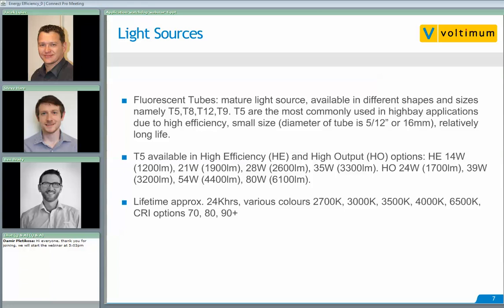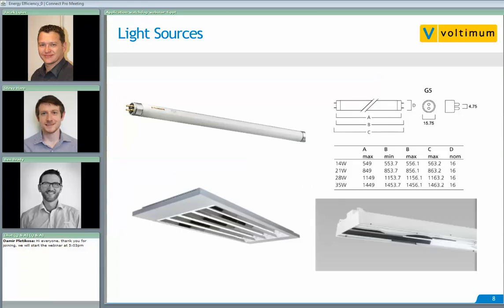T5 fluorescent tubes are available in a multitude of color temperatures, from 2,700 Kelvin up to 6,500 Kelvin, and different CRI options from 70 through to 90 plus — with 90 plus representing color very well. The two pictures show typical high bays, each having about 4 or 6 T5 tubes to provide the desired light output.